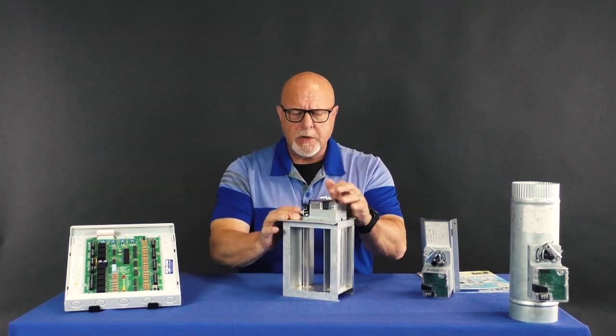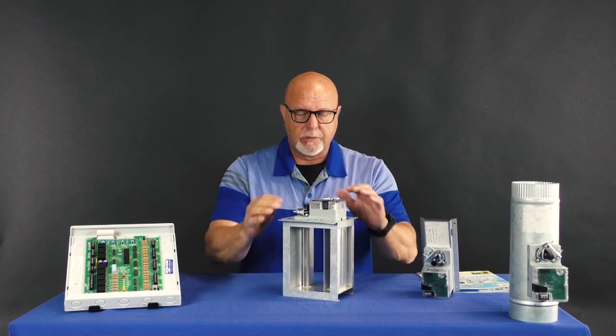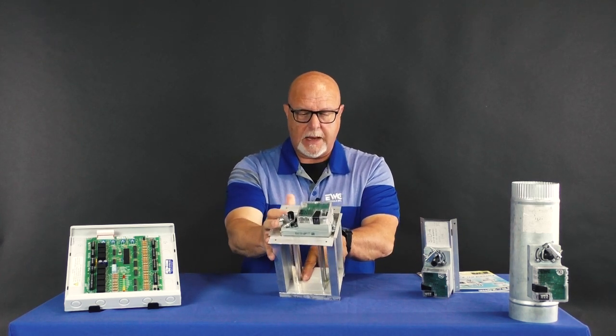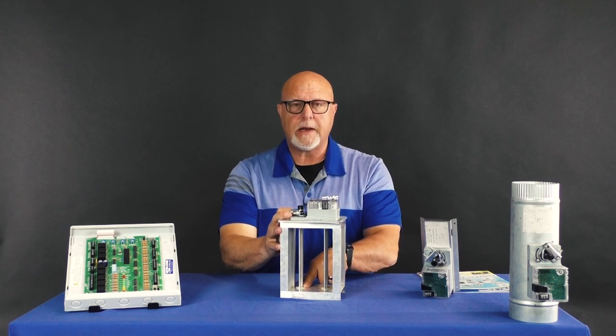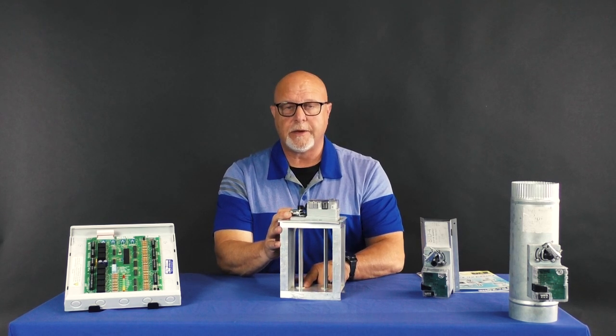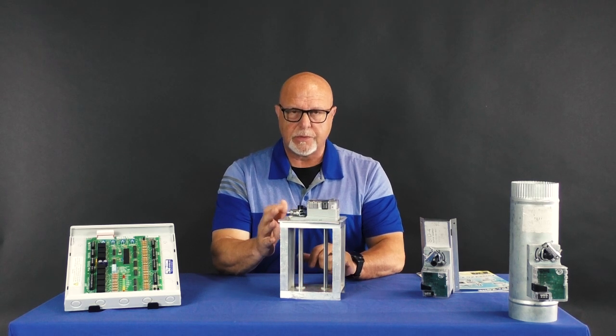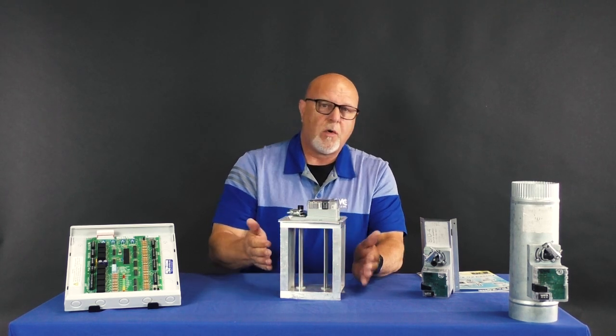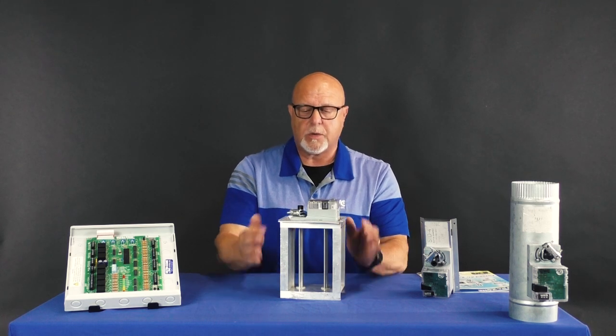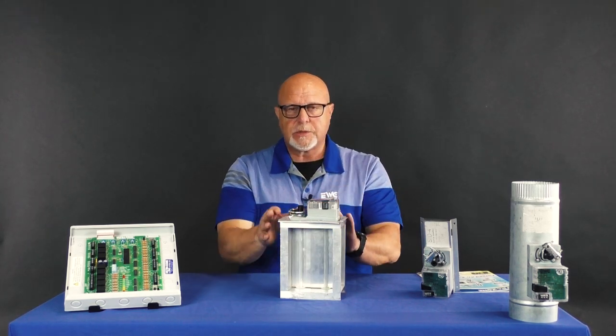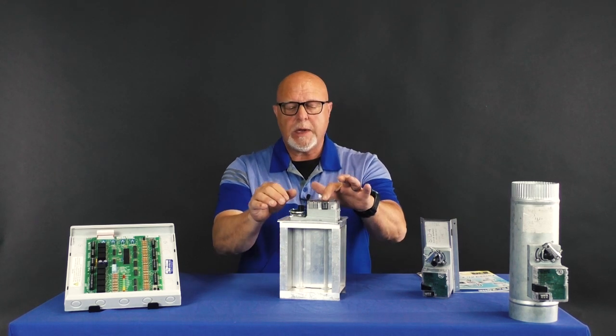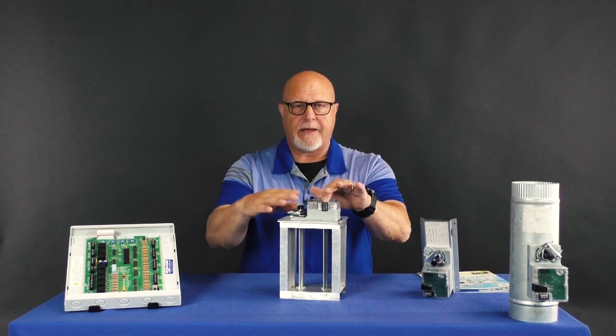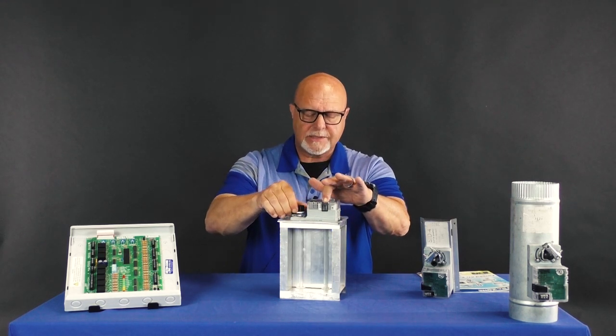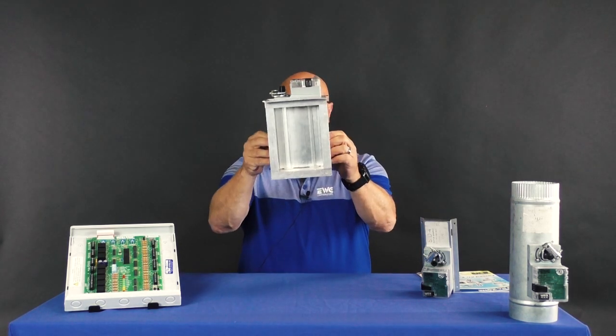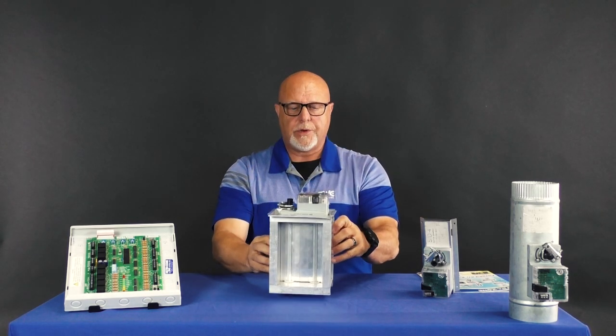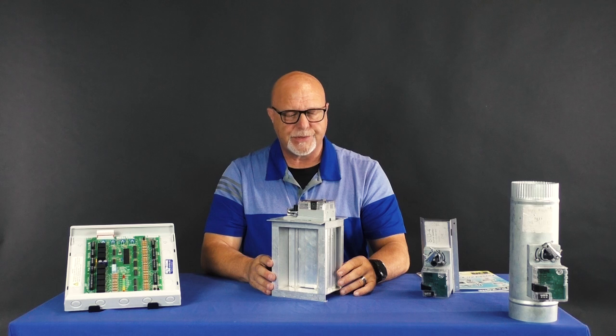All right, so moving along with the construction of this damper, you will notice inside we have nylon bushings that we have incorporated to keep the damper very quiet during its operation. This is very crucial because you need the damper to be able to move, but you don't want it to move very much because of the rattling noise or the whistling that you may get. So this is one of the tightest dampers in the industry. We have 97% closure, less than 3% leakage. You can barely see any light through that when you're looking at this damper. So it is one of the tightest dampers in the industry.